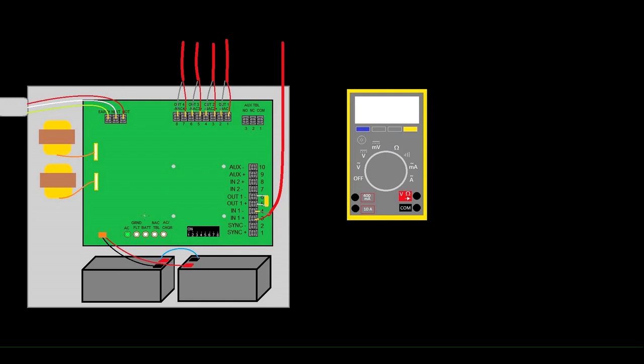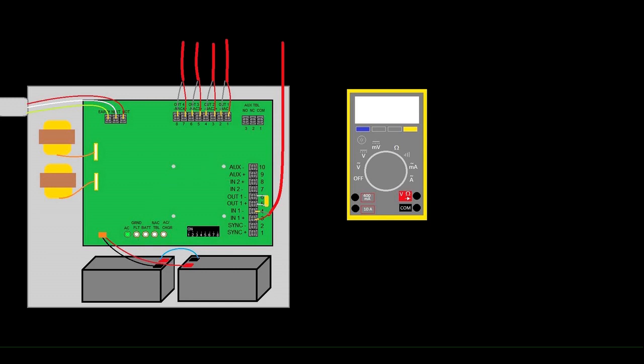As usual I digress, so we're going to talk about ground faults. If you get a ground fault on an FCPS it's going to show up as an open circuit on your trigger unless you have a unique point monitoring the trouble here. So we get to the panel and we see that this ground fault light down here is now illuminated. You don't know what's in ground fault, you gotta troubleshoot it. It could be that any one of your outputs, one of those circuits is touching ground, could be that your batteries are leaking and grounding out. Most likely nine times out of ten it's something on your output.